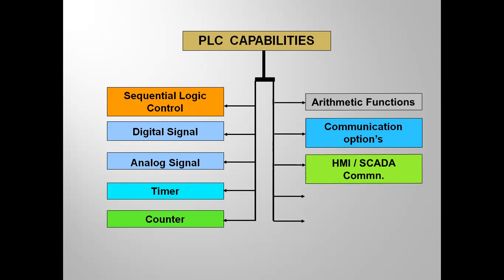For 10 machines, we need one HMI per machine. Whereas SCADA is a separate control room where you can monitor all 10 machines from a distance. SCADA is software installed in your PC or industrial PC at a remote location. I can monitor all the process and also give control commands from SCADA graphics, which go directly to your PLC. PLC controls your machine. PID control is also possible — PID means closed loop controlling with feedback. PID stands for Proportional Integral Derivative.